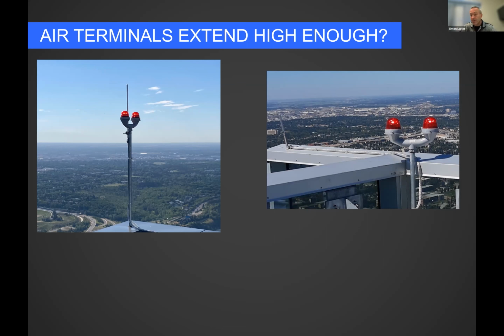On the right-hand side, however, there's the lightning rod out at the end of that parapet that one of our installers had to shimmy out and put on there and didn't enjoy the process. But then you've got that aircraft warning light right there, and the lightning rod only sticks up a wee bit above it. Now, the number in the old code, the 1987 code, was 50 millimeters, 2 inches—you only needed 2 inches of clearance above any particular thing with a lightning rod. Because we harmonized the codes, now we're back up to 10 inches.